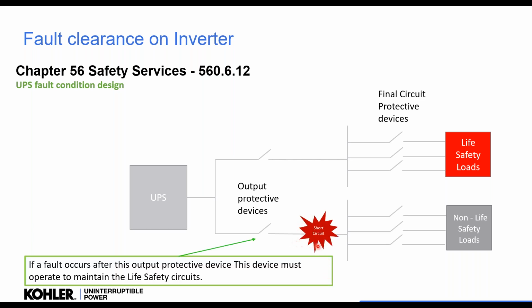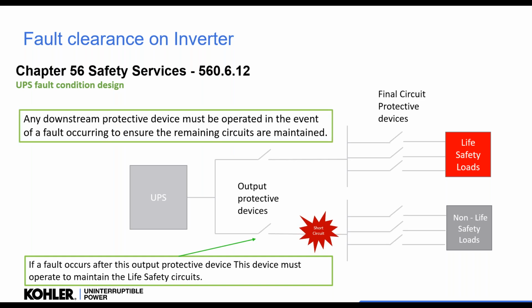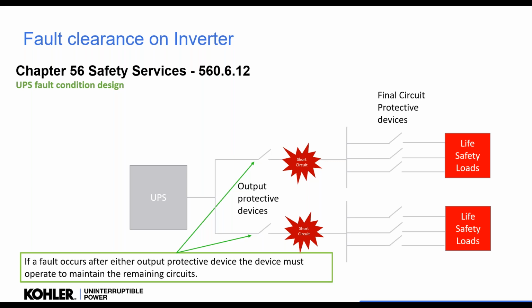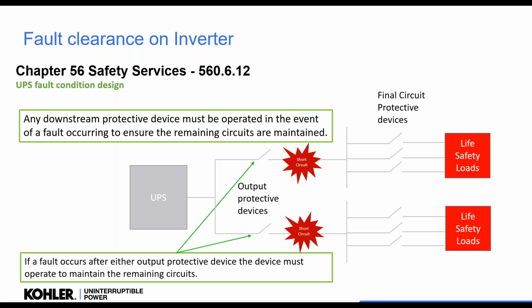If we have a fault occur here on this circuit, we need this device to operate to ensure that all the life safety loads continue to run. It is very critical that we're able to trip that protected device. MCBs on the final circuits tend to be quite small and operate relatively easily. It's not always easy on UPS, but these sub-main devices get a little bit trickier to operate. And of course, if we have two or multiple life safety boards on a central UPS, then any fault anywhere needs to be able to isolate and maintain the rest of the circuits.